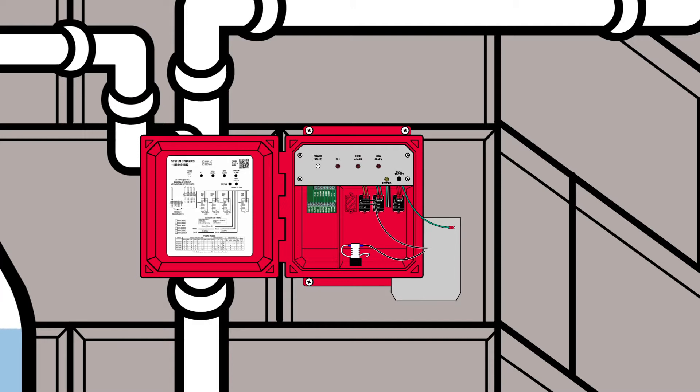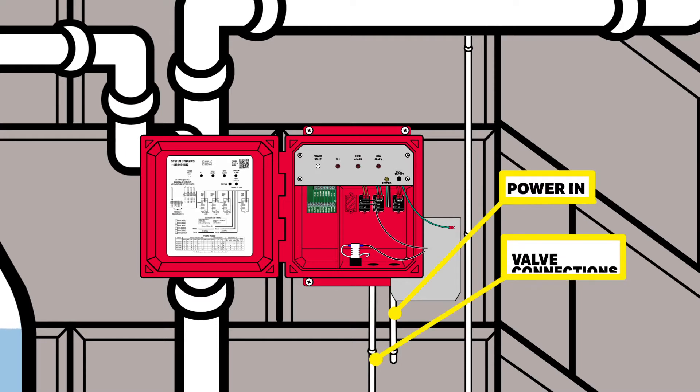If that is not possible, make sure the cross is perpendicular. High-voltage connections, such as the one for power in or the valve operation, should have metal conduits running into the high-voltage area.